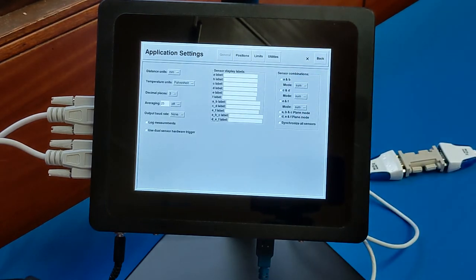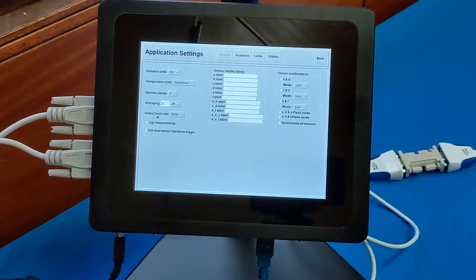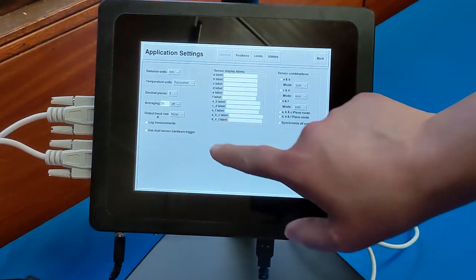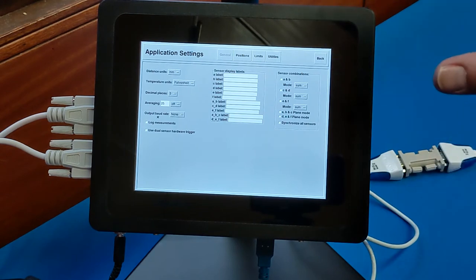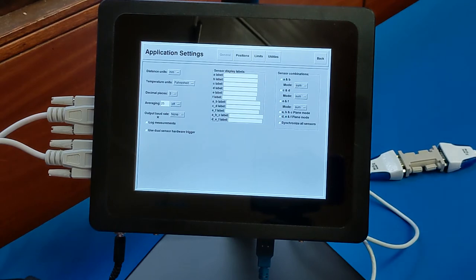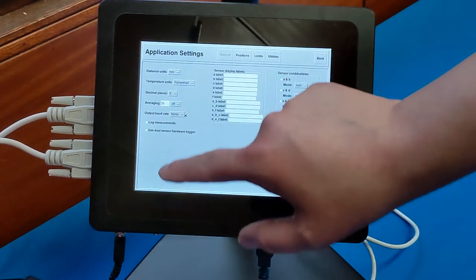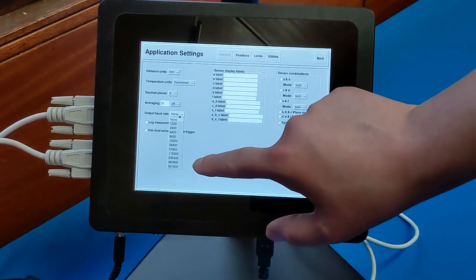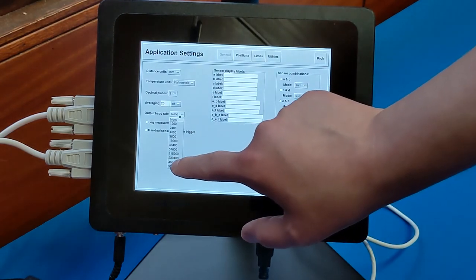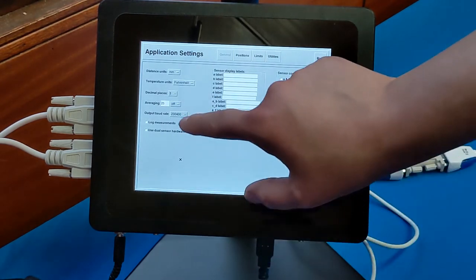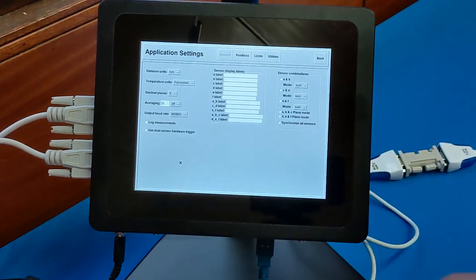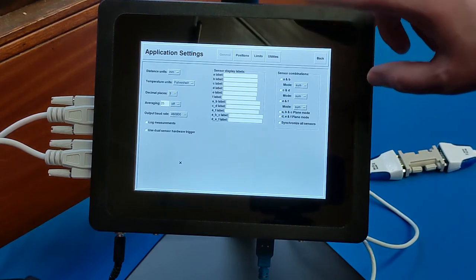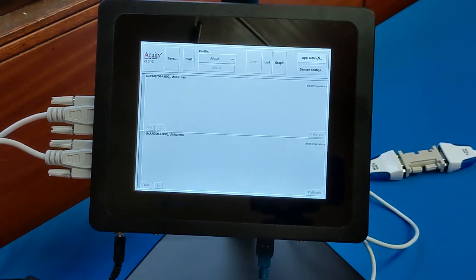Now you'll notice one interesting attribute here, output baud rate. Now that is the output baud rate for the touch panel to another system through the serial to USB cable. So right here, just for purposes of this demonstration, we'll set it at 460,800 baud. Then go back to the measurement screen.